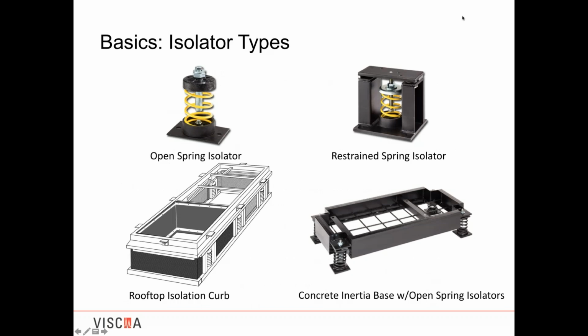All right, now from the basics, on the basic isolator types, as I said earlier on, it could really be any medium, but in general, what we deal with for mechanical equipment is going to be springs or rubber pads. Right now, I'm just showing 4 examples that have springs on them, but it's more to show the attachment and function. A basic open spring isolator will be for a non-seismic, non-wind type of installation where you don't have any tip over concern. The spring itself would need to be stable, and there's a height over diameter ratio for stability. Again, a little bit outside the scope here, but the spring isolation vendor would rarely ever sell you a spring that's going to be unstable when it's installed.